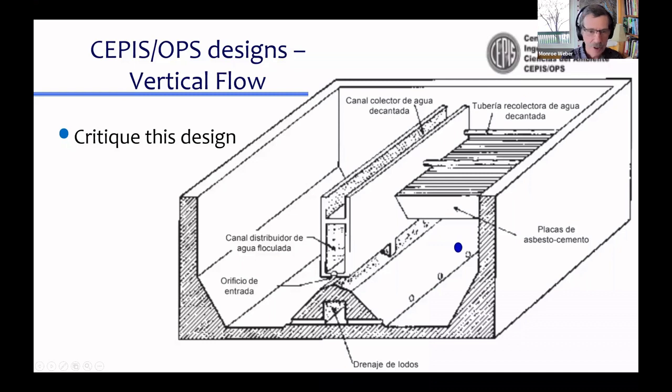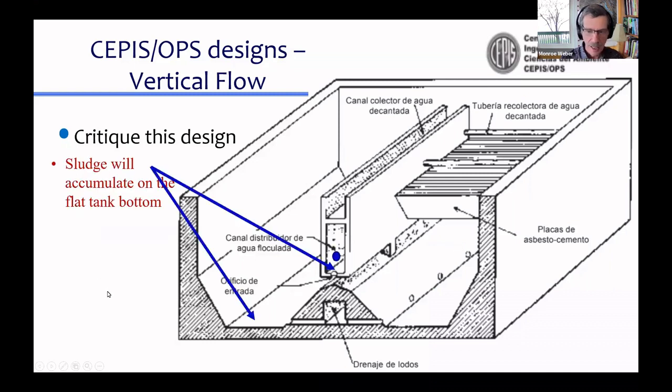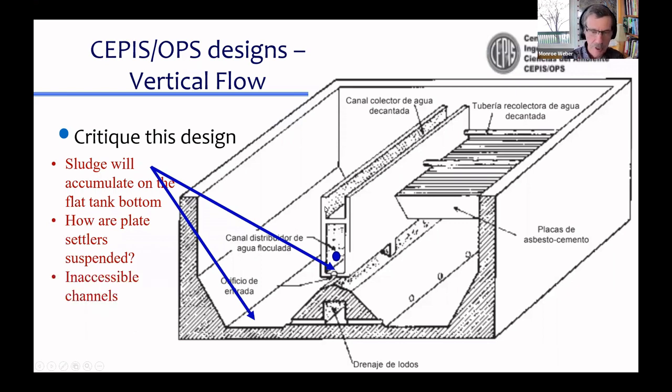Okay, so that was great. Critique the design. You got that one. And I would also say that there's a fair risk that sludge would accumulate inside that channel. I'll show you more about that in a second. And I'm curious how they're suspending their plate settlers.